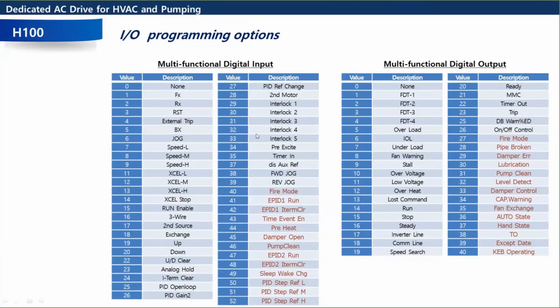5 different interlocks you could program. External trips. Damper open. PID steps. So you could have like a selector switch that switches between different set points. So quite a long list here. Pretty long list for the digital output. So that's where you're talking about relay 1 through 5.